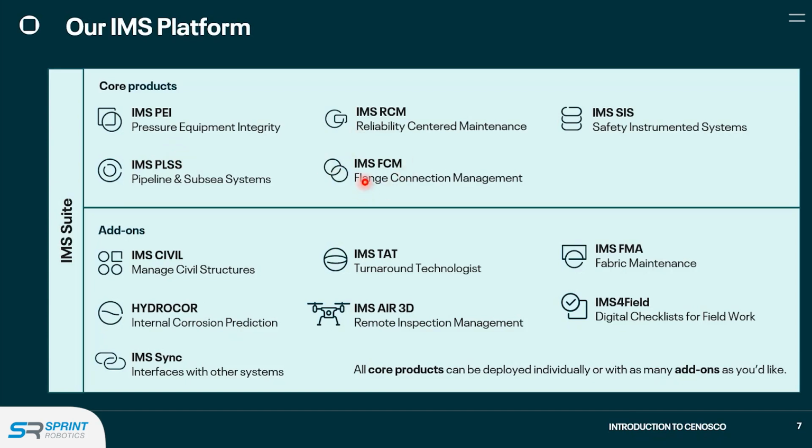FCM for flange connection management calculates torque and tension to create a plan, right? And allows the maintenance crew to perform the maintenance on that flange properly and record the results. It's more like a quality assurance process.